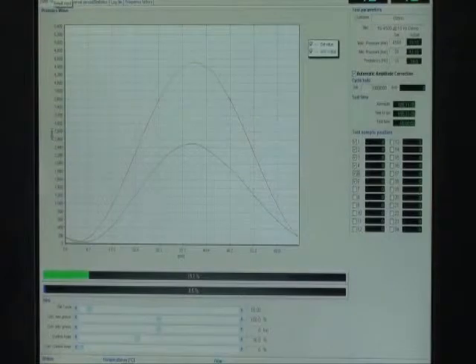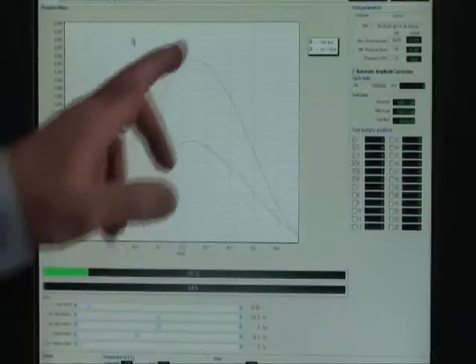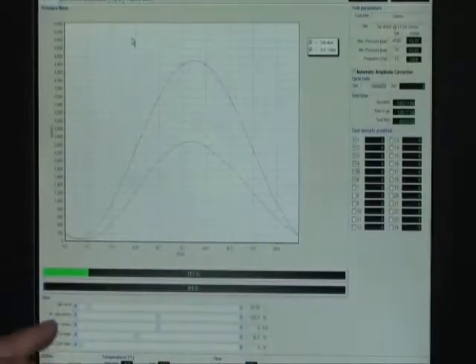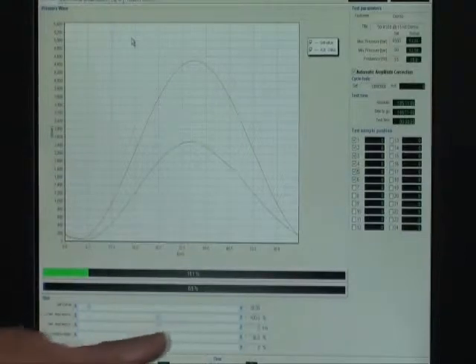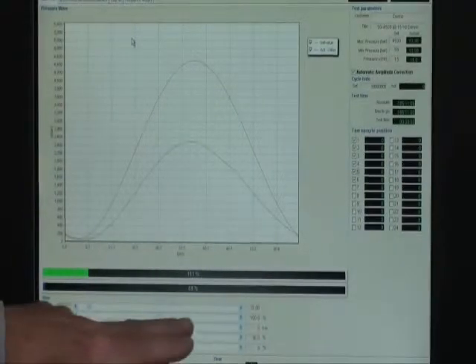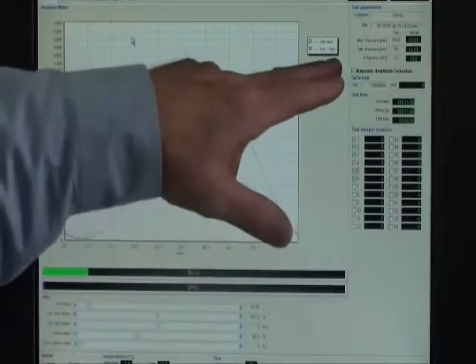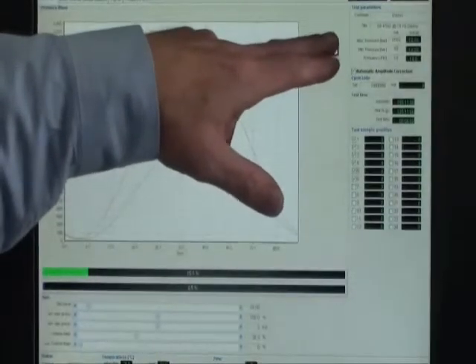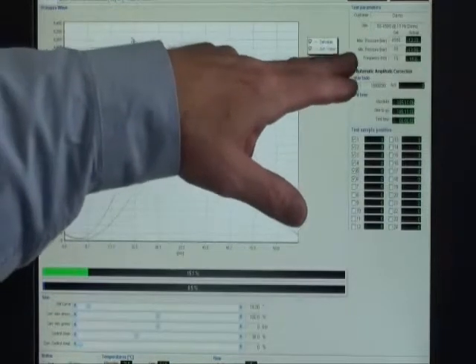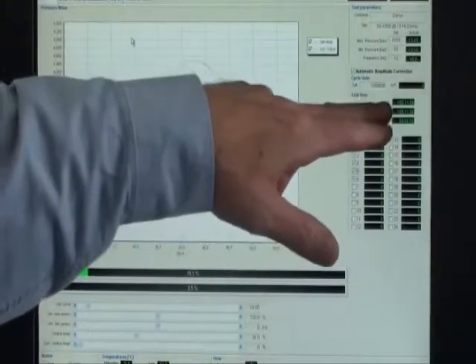On this screen, you can see we have basic sine wave shape. We have the controls we use to optimize the performance of the rig. Here you can see our test pressures. Got a max pressure of 4,500 bar, minimum of 50 bar, and a frequency of 15 hertz. The total number of cycles to run, and the counter. It'll count down from that, it's a 185-hour test, and our sample input.